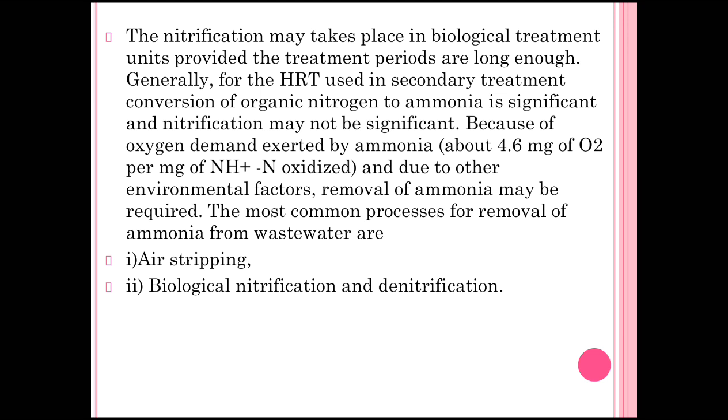Because of the oxygen demand exerted by ammonia, about 4.6 milligrams of oxygen per milligram of NH4+ is oxidized, and due to other environmental factors, the removal of ammonia may be required. The most common processes for removal of ammonia from wastewater are, first, air stripping, and second, biological nitrification and denitrification.